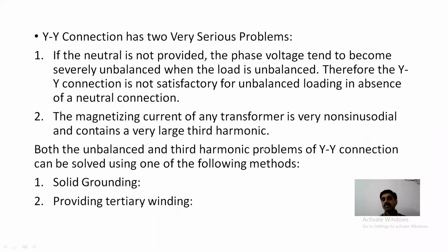Coming to the star-star connection, it has two very serious problems. What are those? If the neutral is not provided, the phase voltages tend to become severely unbalanced. Star-star without neutral connection, when load is unbalanced, because there is no path for the flow of current in the neutral. Therefore, star-star connection is not satisfactory for unbalanced loading in the absence of neutral connection.